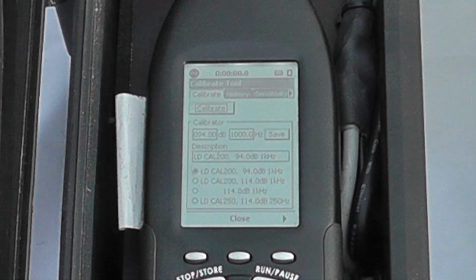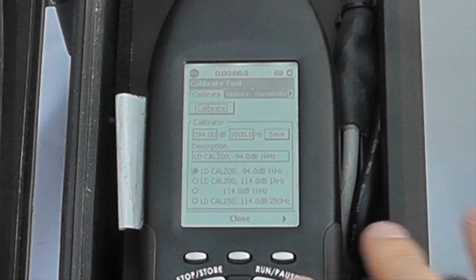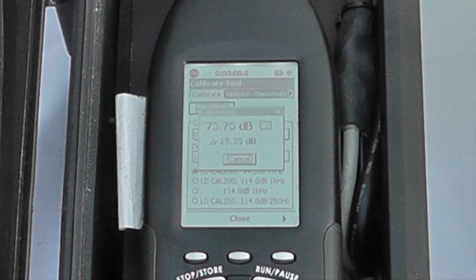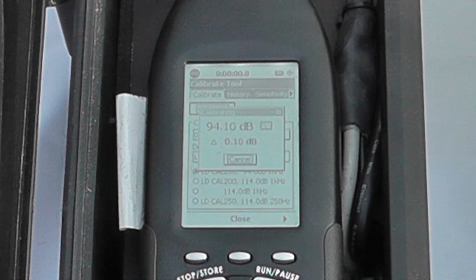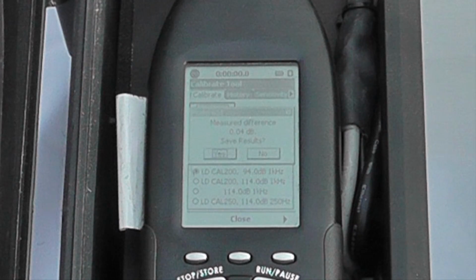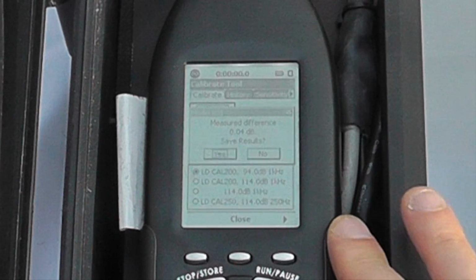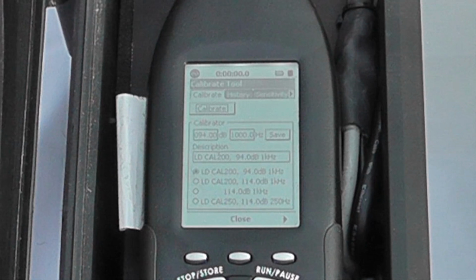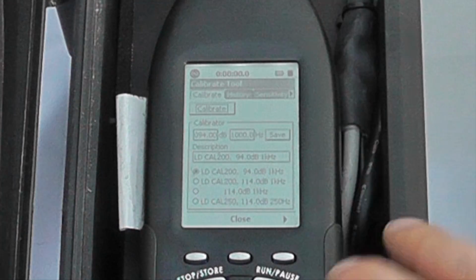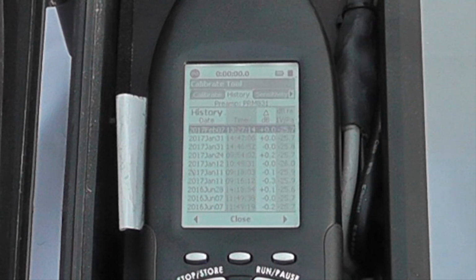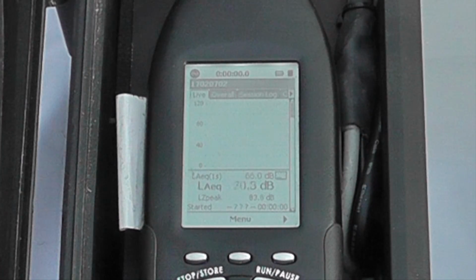So in terms of the calibrate, I'm now going to put it into a calibrate function. I will enable 94 decibels on the Cal 200. I'm sorry you can't see that at the moment because I've obviously got it on the end of the microphone. You'll see I don't have a calibrator on at the moment, but I'll affix the calibrator to the end of the device and we can see we are reading round about 0.04 dB difference. So it's recognised that, and that's the calibration done. Simple as that. So when we want to carry on our next measurement cycle, we know we've got a good integrity tail and we've got a full calibration history, which has now been added today. So that pretty much sums up the 831 operationally.